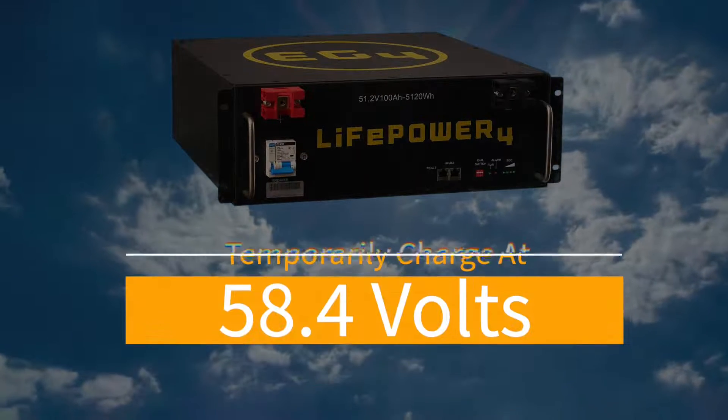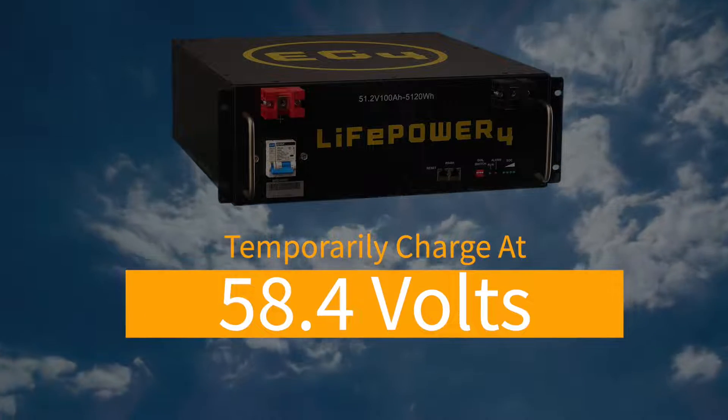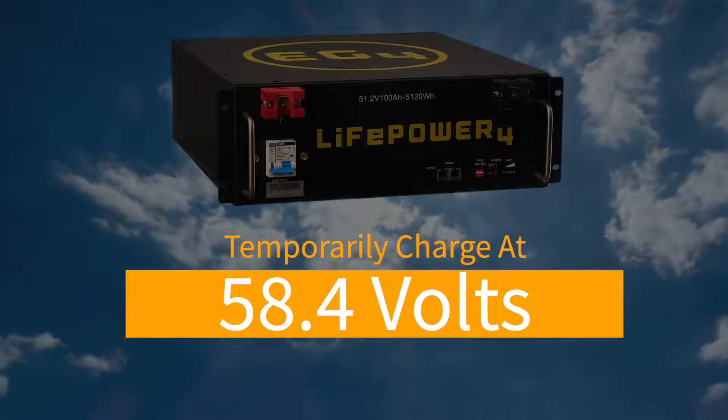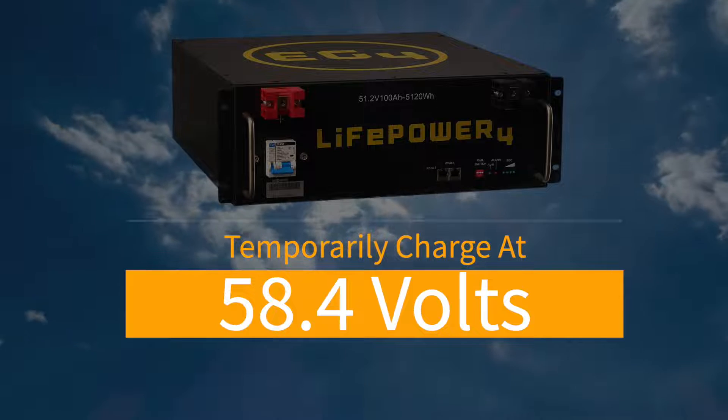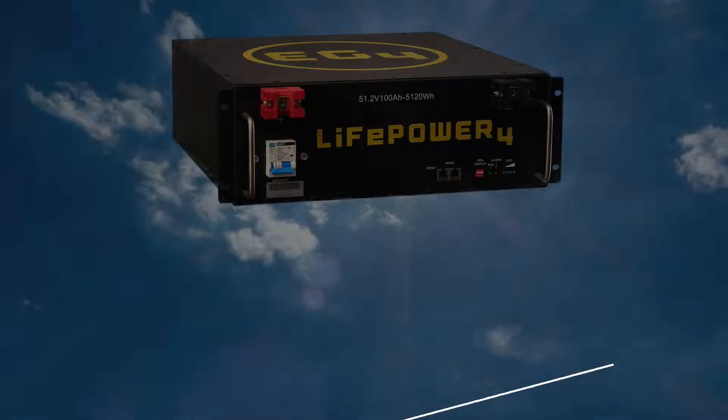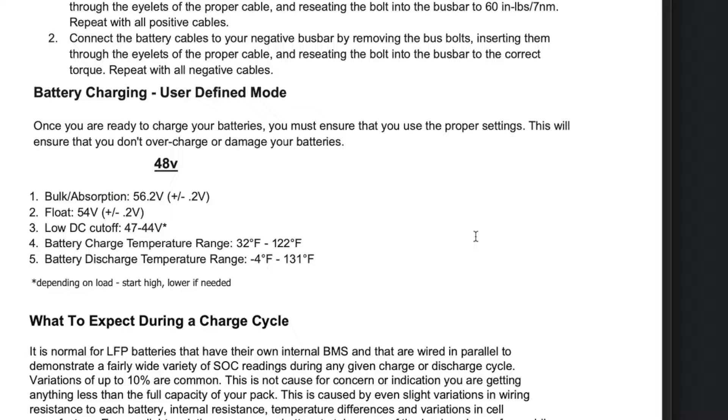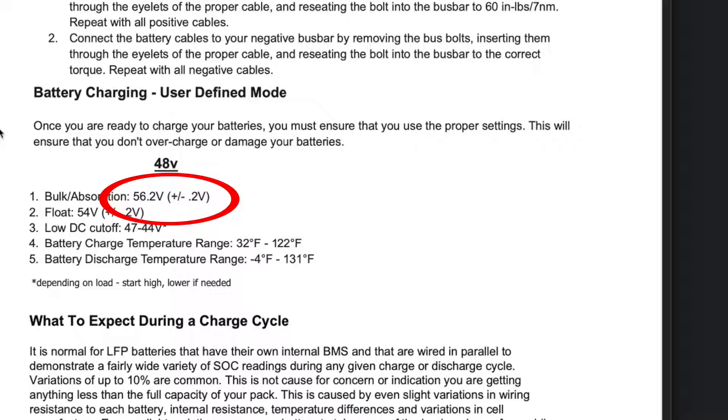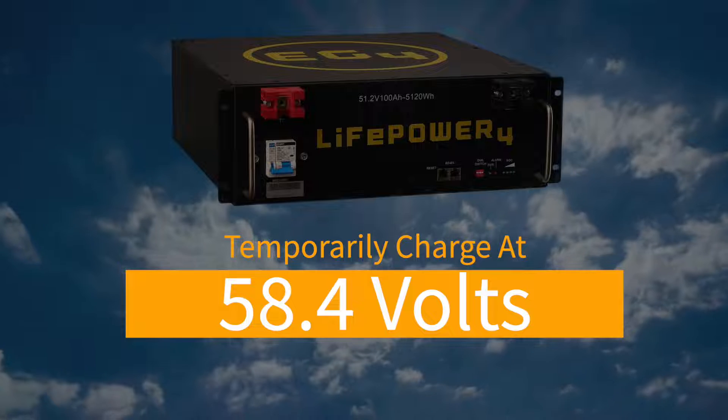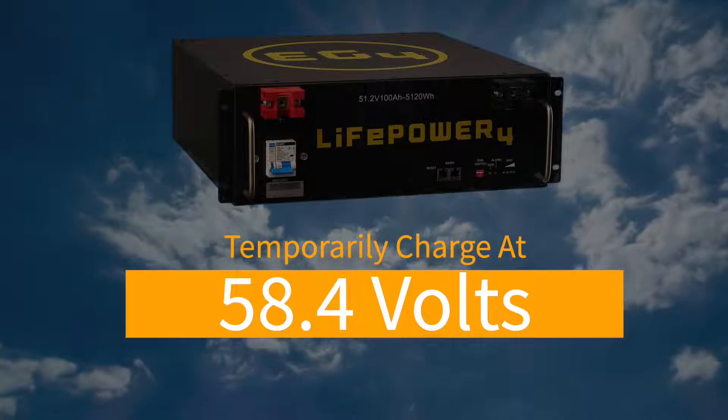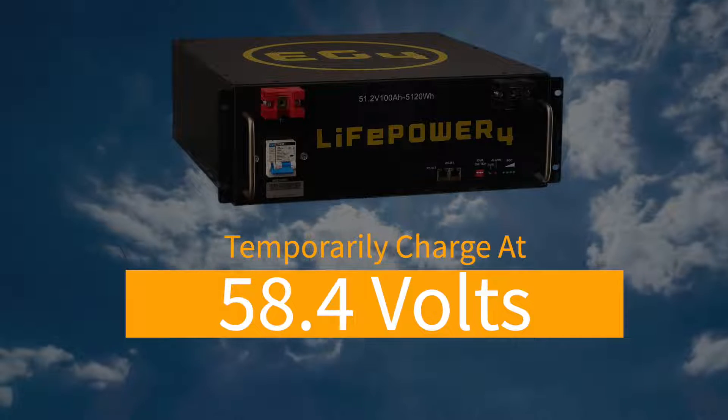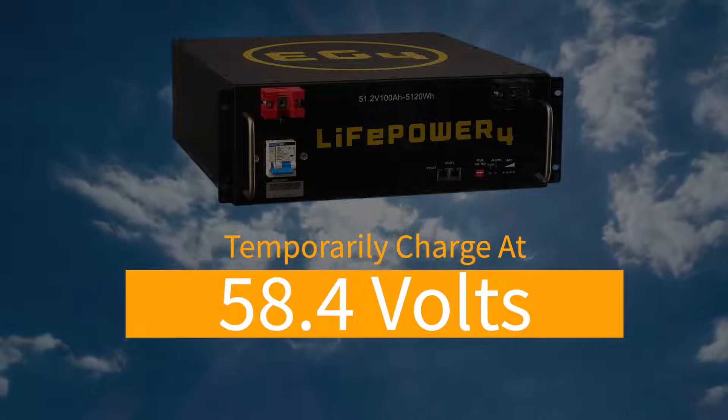And the solution is very easy. We're just going to charge at a higher voltage than normal. We're going to charge at 58.4 volts. This is right from the manual for the battery, 56.2 volts, and that's what I've been charging at. We're just going to raise it up temporarily to 58.4 volts.